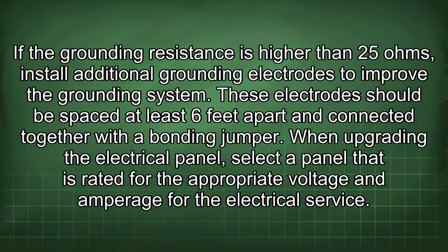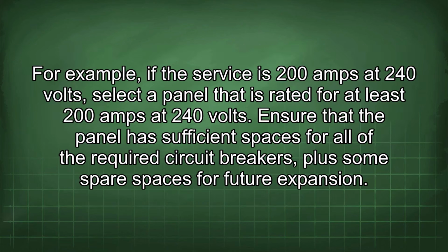These electrodes should be spaced at least 6 feet apart and connected together with a bonding jumper. When upgrading the electrical panel, select a panel that is rated for the appropriate voltage and amperage for the electrical service. For example, if the service is 200 amps at 240 volts, select a panel that is rated for at least 200 amps at 240 volts.